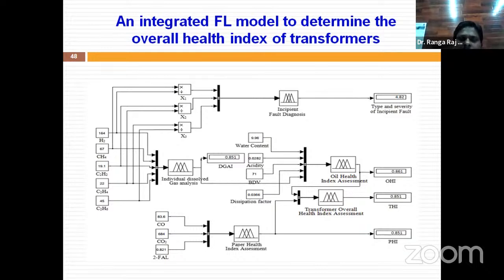We also need to know what type of problem or fault is present in the transformer, generally called incipient faults — whether it is a low, medium, or high temperature fault, partial discharge, low or high arcing, or burning. We should determine the severity and type of fault alongside the health status. Only then will it be an exact analysis, so that we can reduce the fault and improve the performance of the machine. Taking a decision based only on health condition, while ignoring the fault level, is not good.